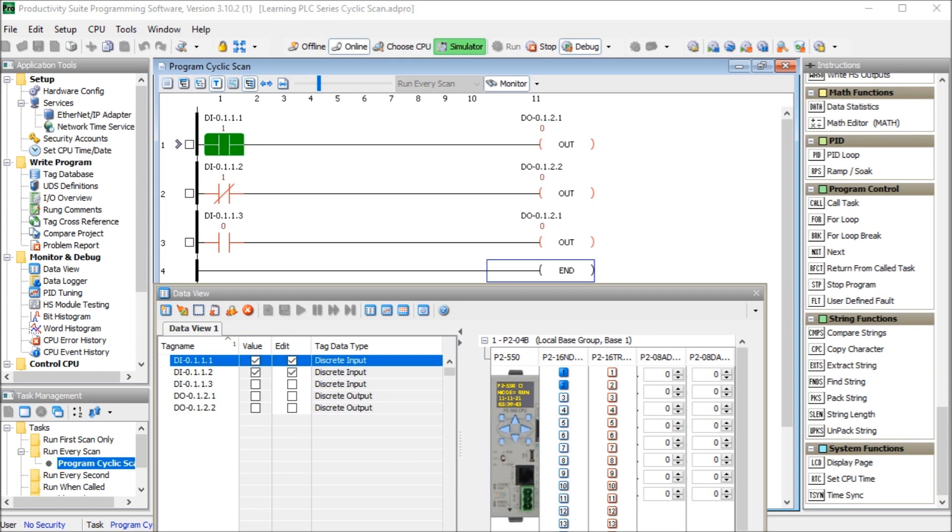The PLC scan update outputs. All of the physical PLC outputs are written at least once during each scan. The outputs are determined by the ladder logic program code. So once we've done through the code and we hit the end statement, then the output logic gets updated.